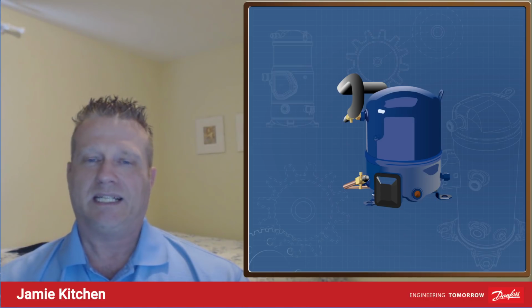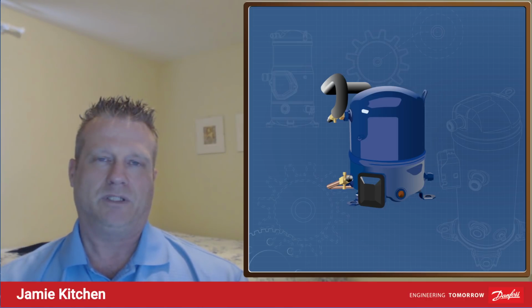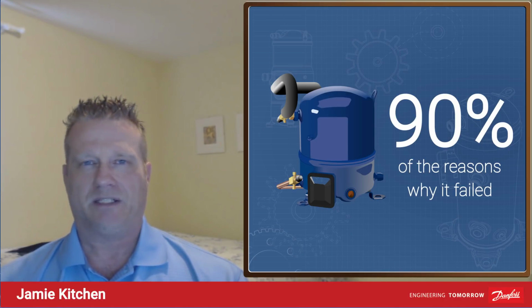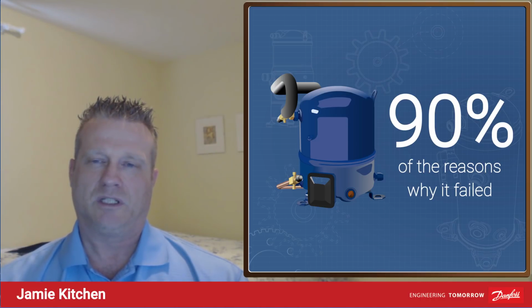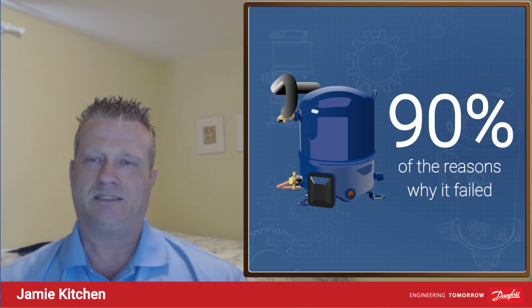So what we're going to talk about today, and we're going to focus on compressors, is how you can do a quick inspection, preventive maintenance, or, if you are replacing a compressor and doing a startup or commissioning, how you can eliminate 90% of the reasons why it failed in the first place. Replacing something and not knowing why it failed is probably the ultimate version of gambling. If you haven't eliminated that issue, chances are it's going to fail again. We've seen this in the field where you get your third compressor back from the same installation, and suddenly everybody connects the dots, digs their heels in, and finally figures out we've got to figure out what's wrong here.